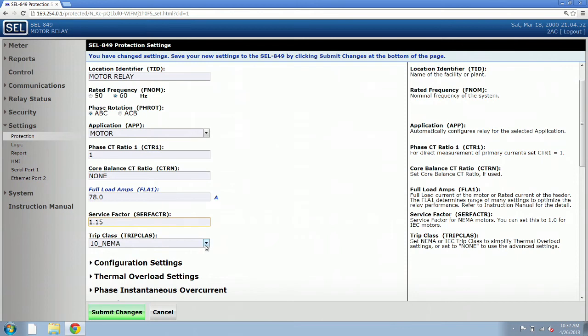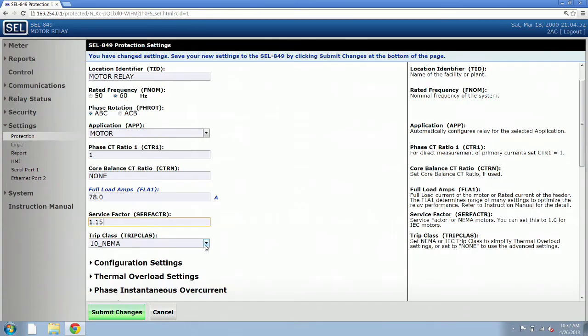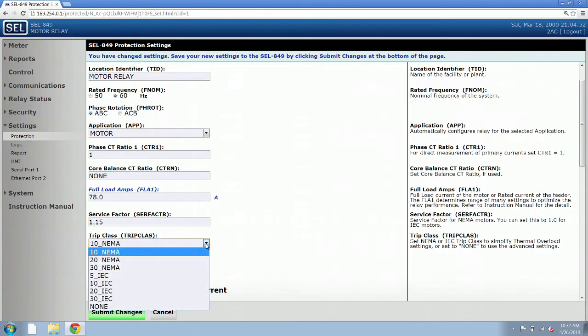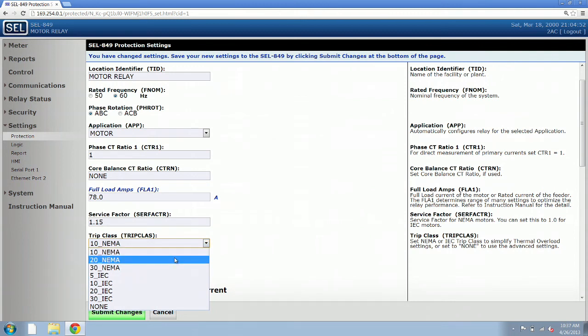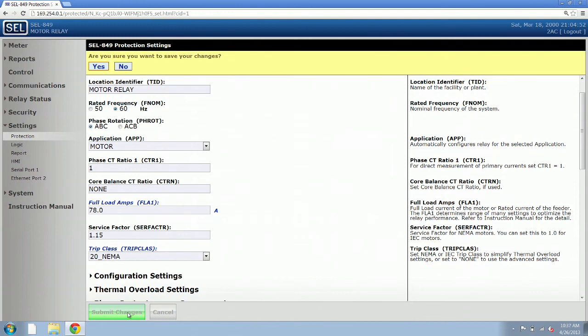Then we need to set the trip class. The trip class basically says how fast should the relay trip the motor offline in an overload condition. We can often get that off of the existing electromechanical relay if there is one already. We've determined that our trip class is a NEMA 20. We select that and click on submit changes.